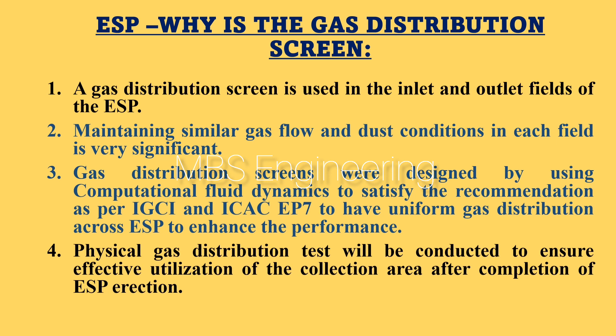Point 3: gas distribution screens were designed using computational fluid dynamics (CFD) to satisfy the recommendation as per IGCI and ICAC EP7 to have uniform gas distribution across the ESP to enhance performance. Point 4: a physical gas distribution test will be conducted to ensure effective utilization of the collection area after completion of ESP erection.